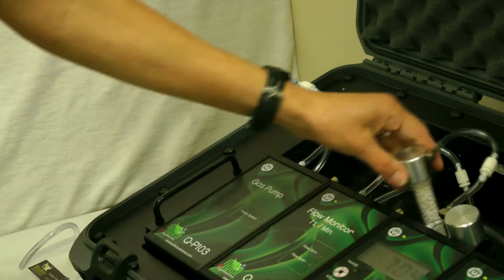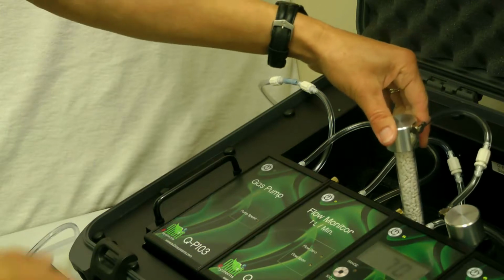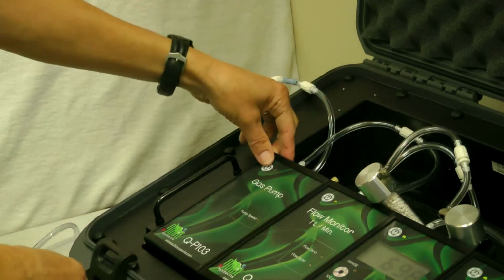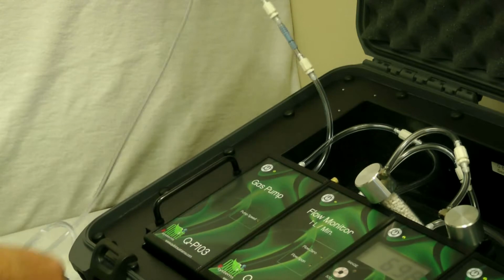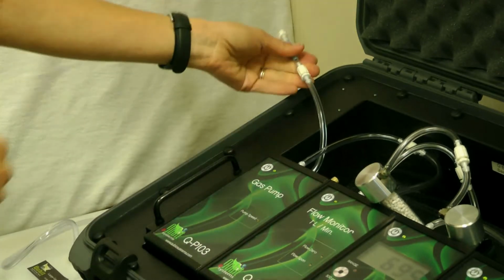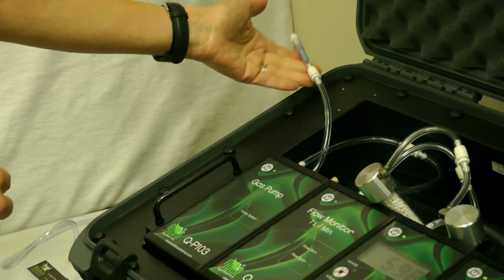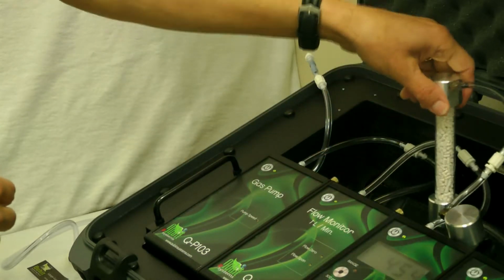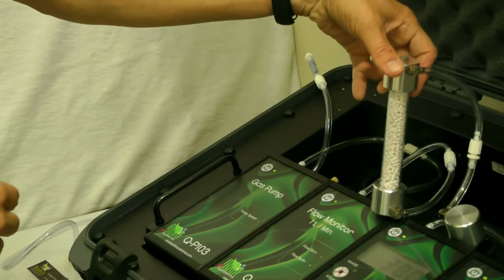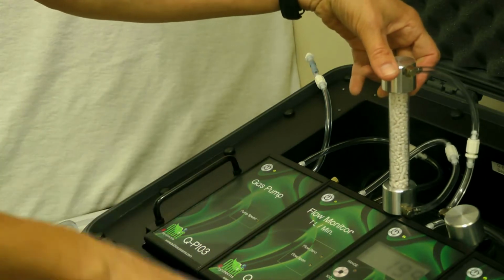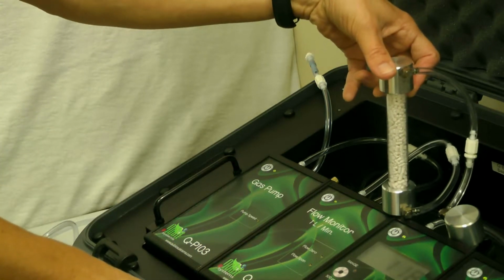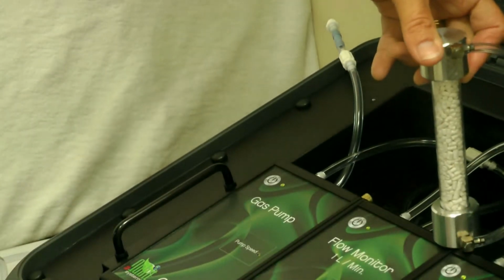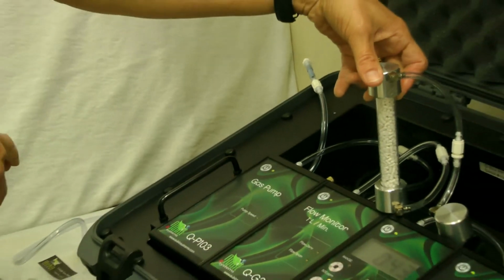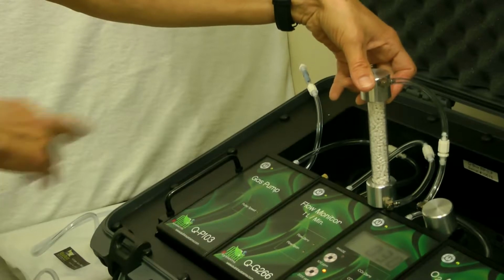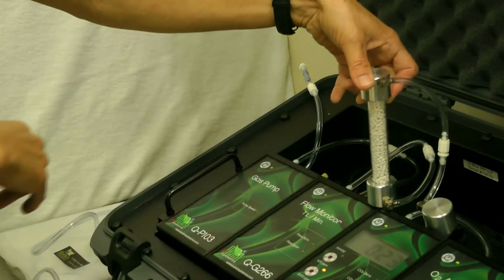So in this setup right now, when the pump is turned on, the gas is being carried from outside room air through the system, through the soda lime column, which will scrub any CO2 that's present in the air and bring the CO2 analyzer to your 0 position. You can see the readings are dropping right now. And when you do reach your 0 CO2, if the 0 is exactly 0 as it's shown on the display, then there's no need to do anything.